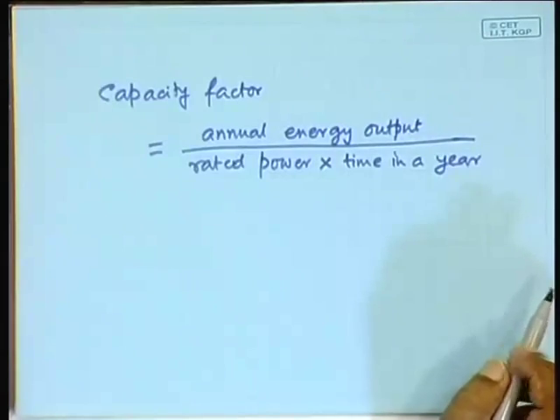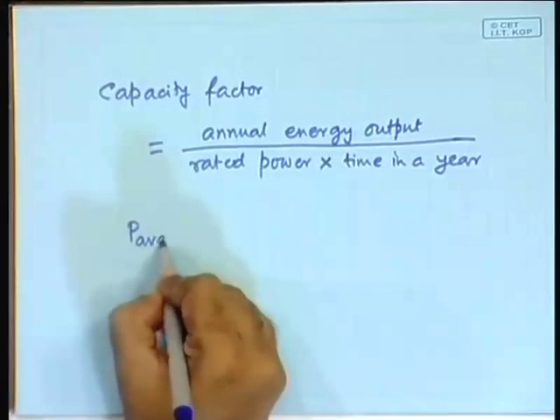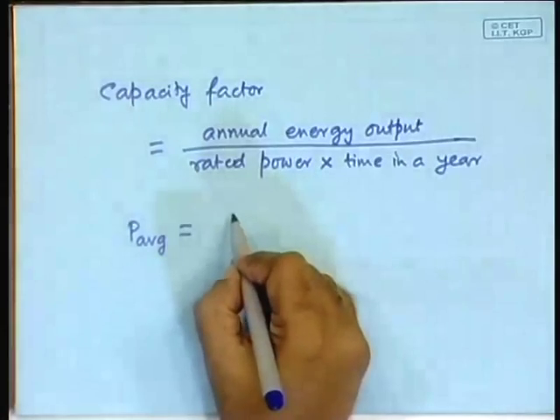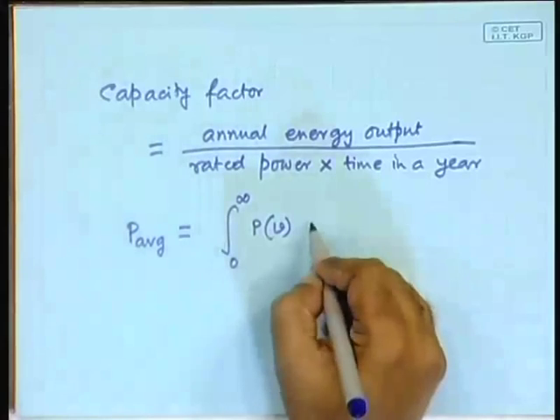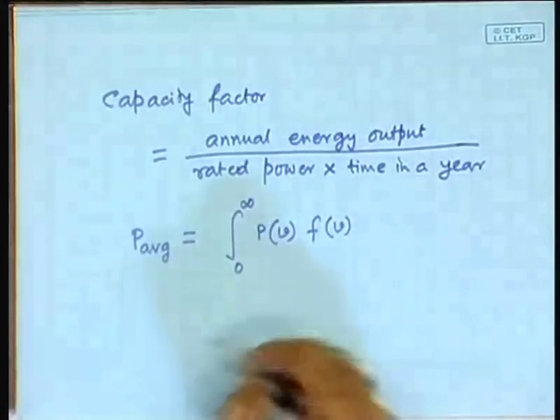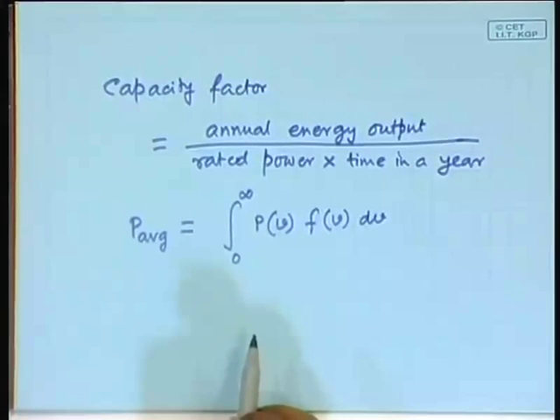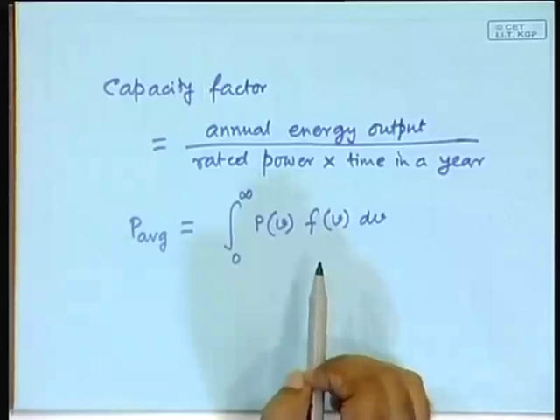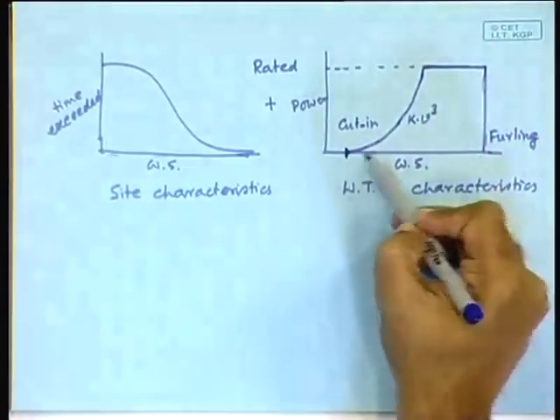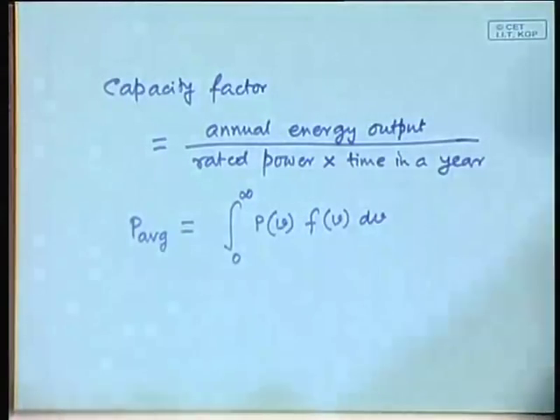The numerator is the average power generated — that is the integral of power as a function of wind speed times the probability distribution of wind speed. This integral normally has to be obtained graphically. But under the assumption that the characteristic is exactly of this type — no generation below cut-in, exactly cubic after that, and exactly flat at rated power — it can be somewhat analytically obtained.